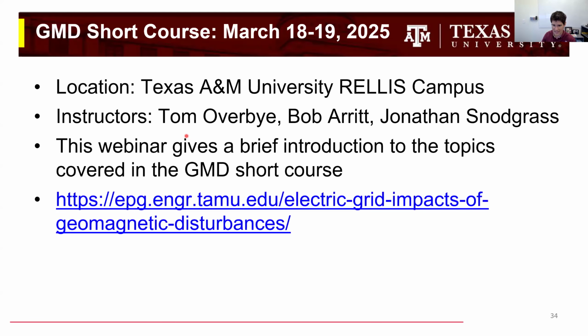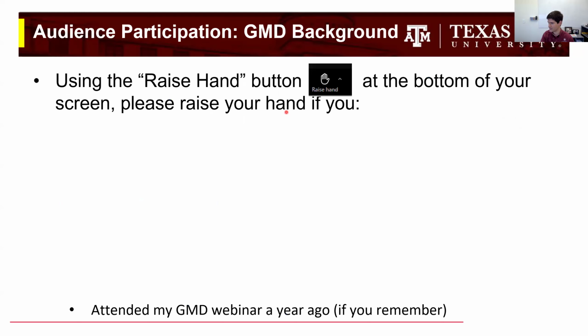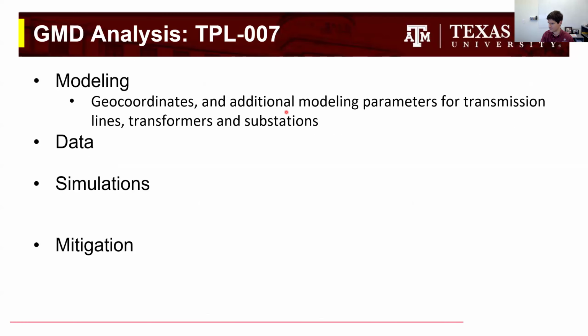Awesome. Someone asked in the chat what type of grid model the state estimator needs to perform the voltage estimation. Great question. It would be a standard GMD assessment model. So going back to, sorry, I'm going to give everyone whiplash. It needs the GMD model. It needs geocoordinates, and it needs the parameters: the DC line resistance, the transformer type, and the substation grounding resistance.